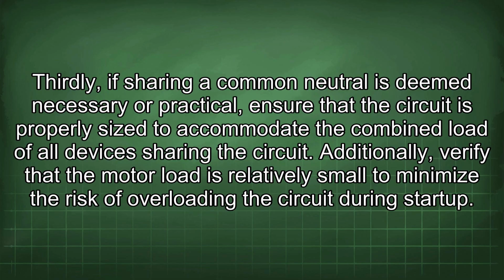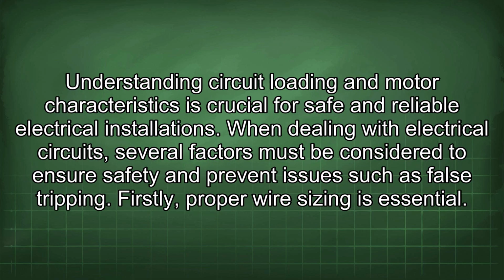Thirdly, if sharing a common neutral is deemed necessary or practical, ensure that the circuit is properly sized to accommodate the combined load of all devices sharing the circuit. Additionally, verify that the motor load is relatively small to minimize the risk of overloading the circuit during startup. Understanding circuit loading and motor characteristics is crucial for safe and reliable electrical installations. When dealing with electrical circuits, several factors must be considered to ensure safety and prevent issues such as false tripping.